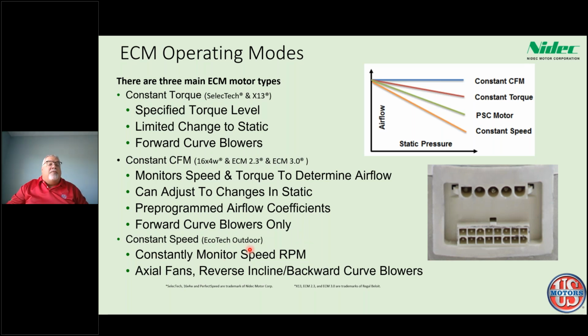And then finally we have a constant speed, and I won't talk much about these today. I just want to give you the overview of ECM, that there are some constant speed motors out there. A perfect example is your outdoor condenser fan ECM products. We have an outdoor EcoTech, and I know that there are other products out there as well. Basically, you give it a speed or an RPM, and that's where that motor runs. As static pressure increases, it doesn't know where to go either. It overloads, and it's only going to move so much air based on the RPM. So those are the three modes of operation.